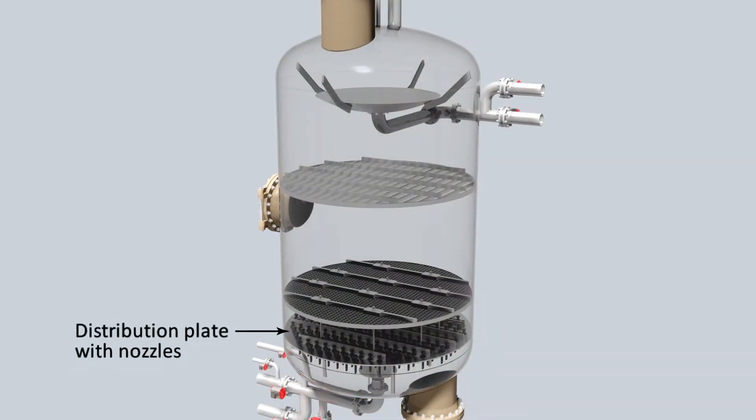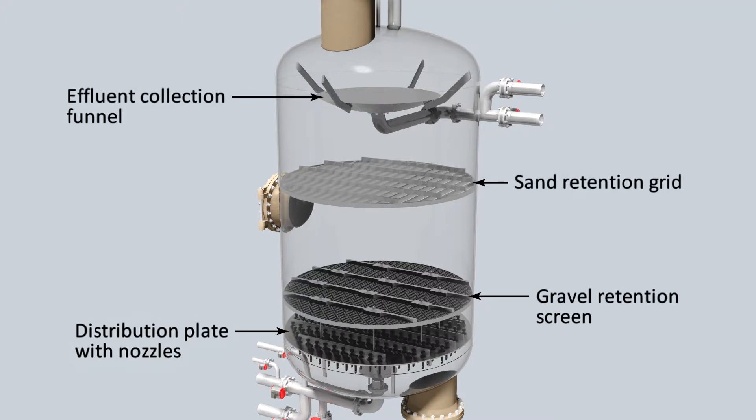Upflow filtration provides full bed penetration enabling solids loading rates four to six times higher than conventional downflow filters.